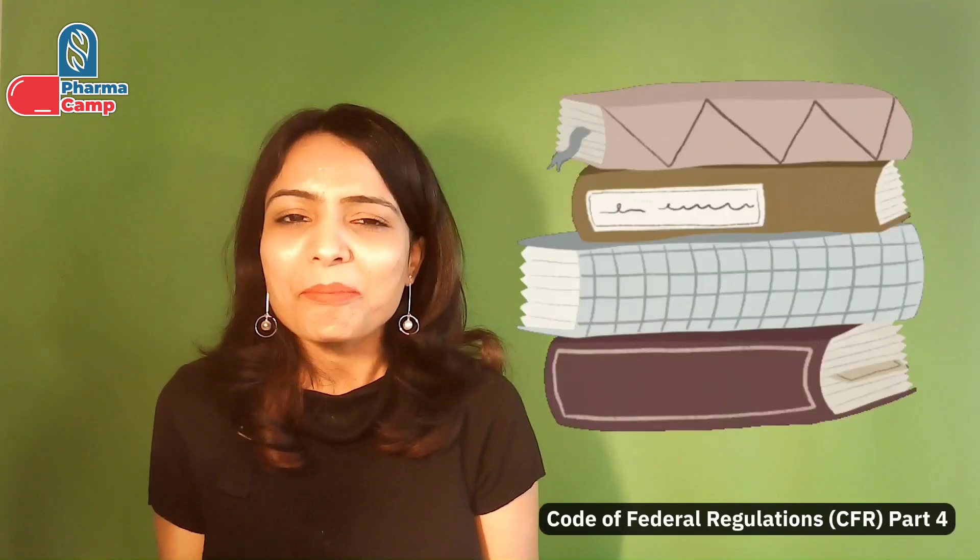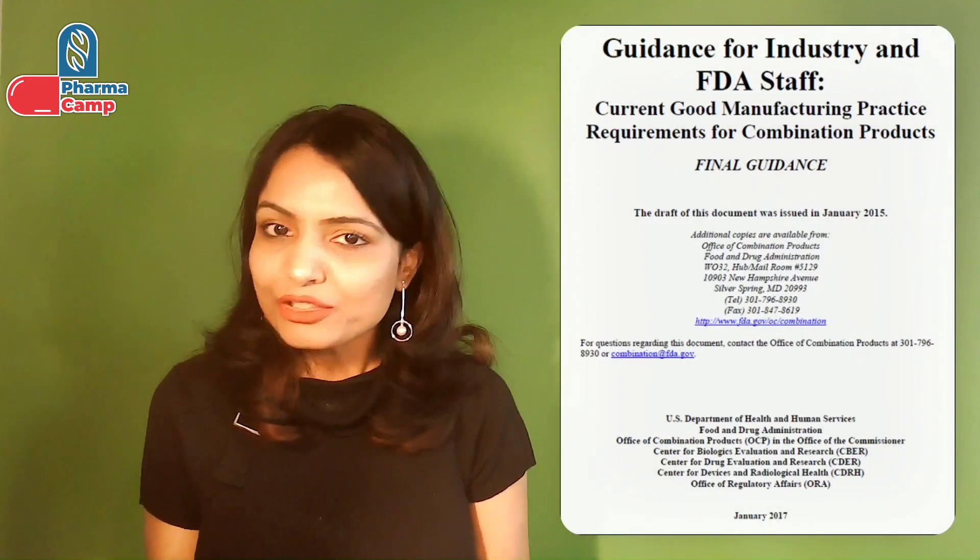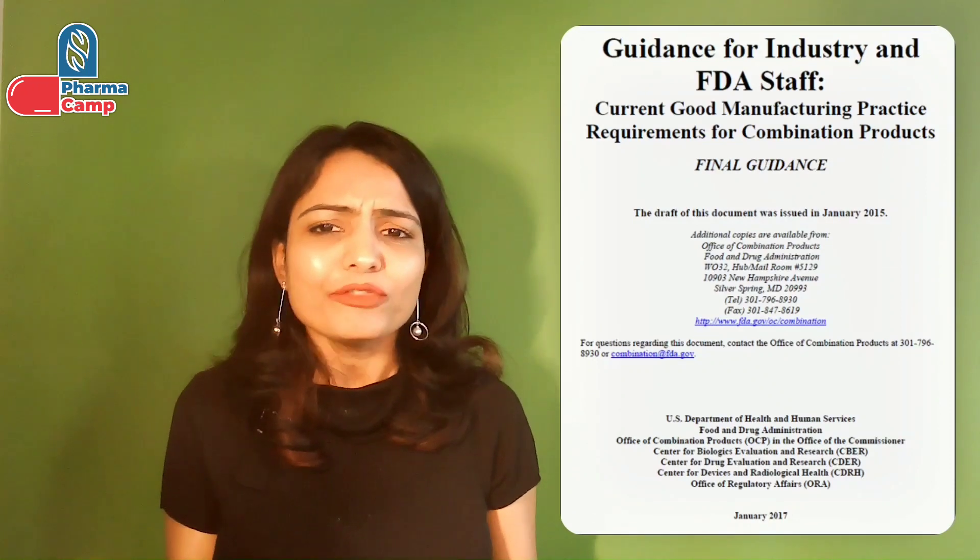Let's start first with the US. As I explained in detail in the first video of this series, in the US there is a separate regulation related to combination products. Combination products are regulated by FDA — CDER, CBER, or CDRH — depending on the primary mode of action of the product. The GMP requirements for combination products in the US are outlined in CFR Part 4, which specifies that combination products must comply with both drug and device GMP requirements.